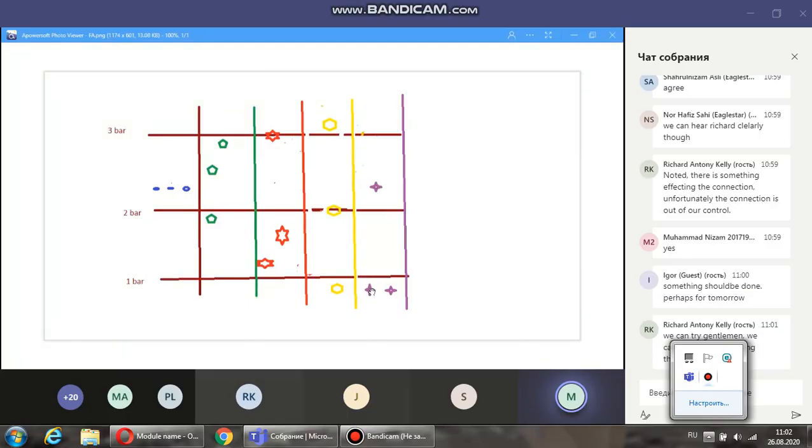Of course, now you know since this is nearby, the gap is too much. This will be the average pressure. Let's say 0.7 bar. You will have already got an alarm, low lube oil. And if you do not take an action quickly, you can have a shutdown because the pressure may go below 0.5 bar. What do you think that you should do now? If you allow it to continue, the pressure may drop further because the sensors are not correct.